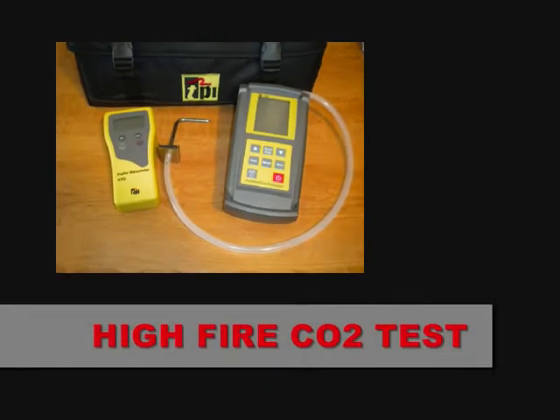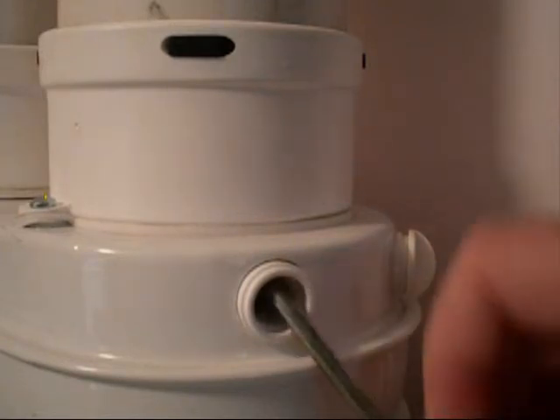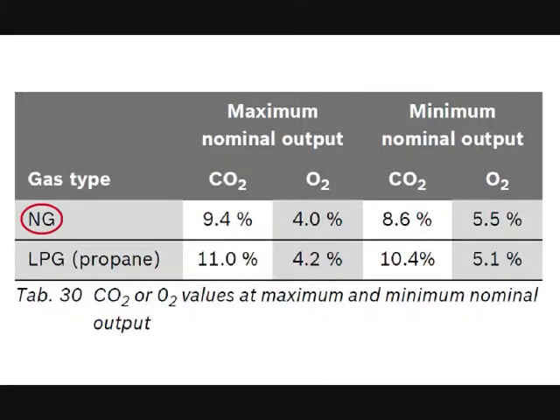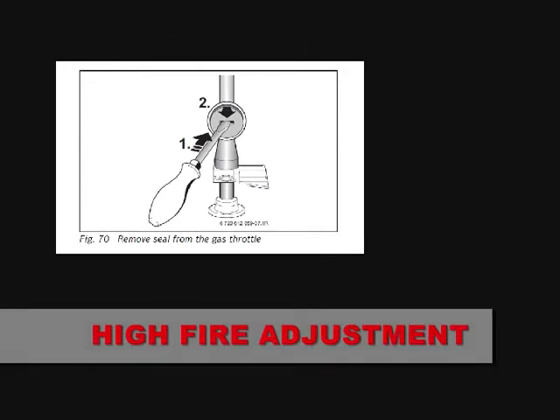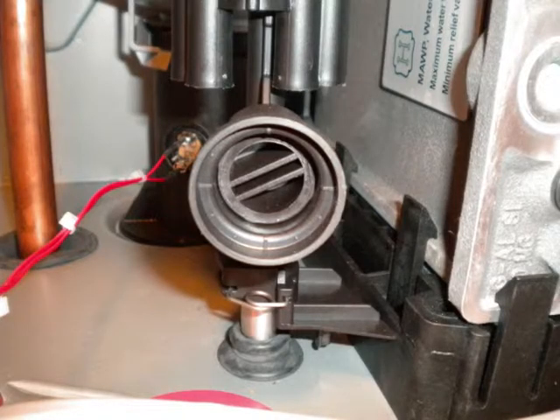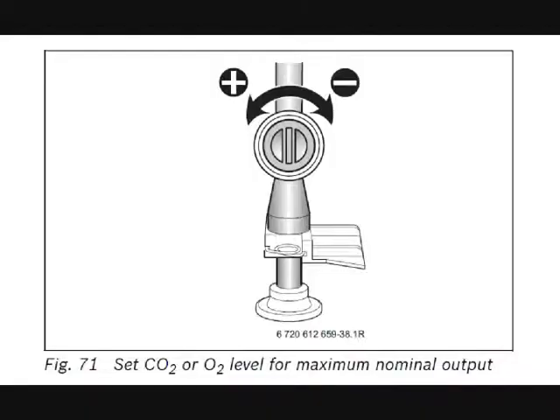Using a combustion analyzer, take the high fire CO2 reading by removing the test port on the vent adapter assembly, inserting the combustion analyzer probe, and allowing the readings to stabilize. For natural gas, the maximum CO2 output should be 9.4%, as shown in Table 30 on page 77 of the install manual. If adjustment is required, remove the seal from the gas throttle and make very slight adjustments using a slotted screwdriver. Counterclockwise increases CO2 levels. Clockwise adjustments decrease CO2 levels. Allow readings to stabilize before making additional adjustments.